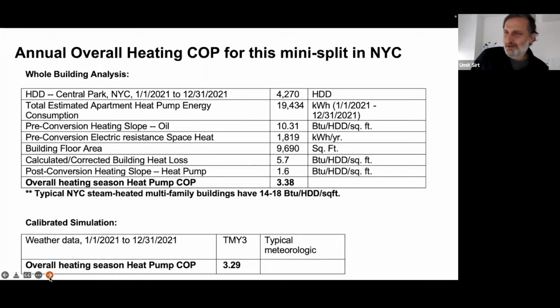There's been a lot of discussion about the annual overall heating COP for a heat pump. In our whole building analysis we found it to be about 3.38, between 3.35 and 3.4. Our calibrated simulation model came out to about 3.29, or 3.3. I'd say calibrated simulation is more granular and detailed. So if you're an engineer in New York City doing a high-level calculation for your building, I'd suggest using somewhere between 3.3 and 3.4. You'll need to multiply your energy use by the thermal efficiency and distribution losses, then divide the building heat load by 3.3 to estimate the likely electric consumption after conversion.